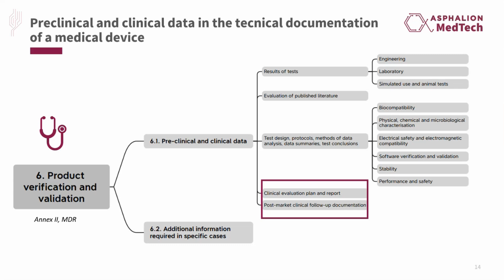But when new clinical data needs to be generated through a clinical investigation, part of the documentation required is the investigator's brochure. The contents of this document are specified in section 2.5 of Annex 15 of the MDR and should be submitted to a competent authority in each member state where the clinical investigation will take place. This investigator's brochure contains all the relevant preclinical data or summaries of this data, and the clinical data generated through the clinical investigation will then be included in the clinical evaluation of the medical device.